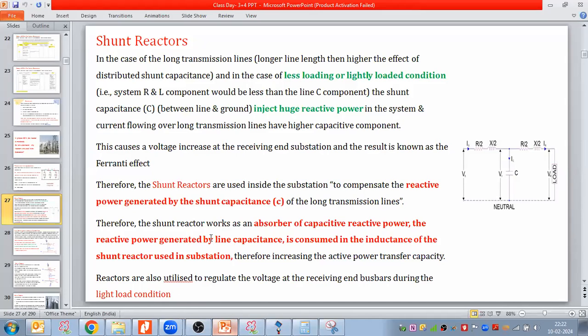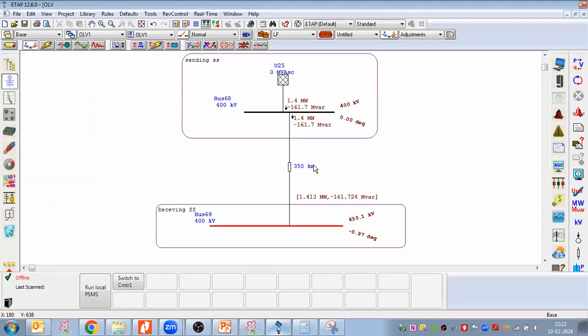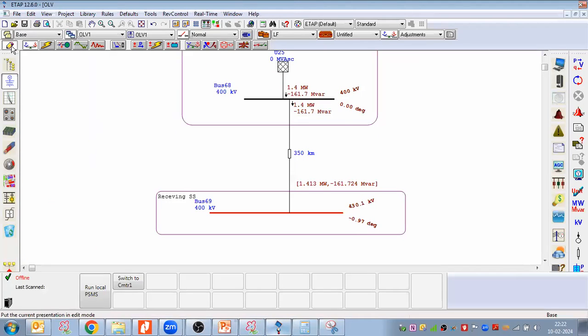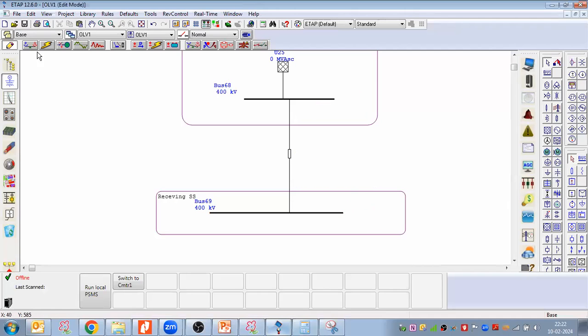So now, let us take the shunt reactor in the substation. How do we take the shunt reactor? We don't have the shunt reactor element in this ETAP, so what we do is take a static load. In here we have the loads, and like here we have the source - for the source we have the grid and the generators.